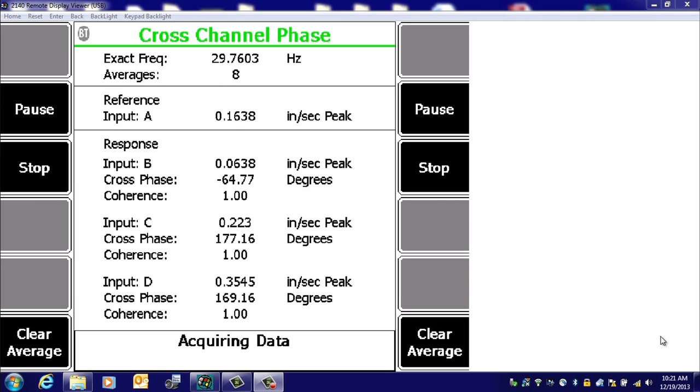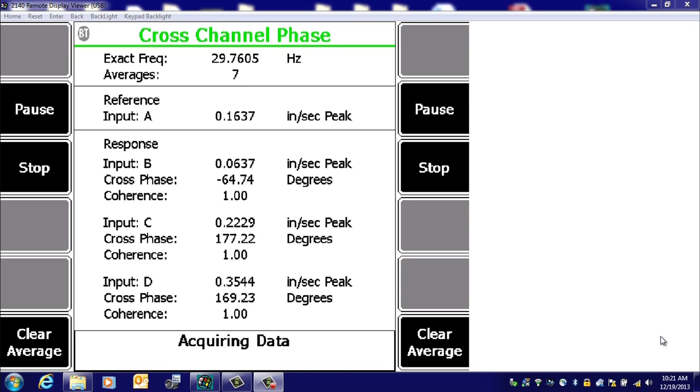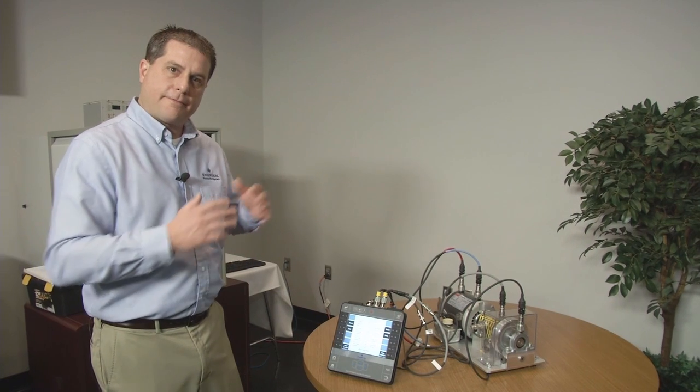But notice the cross-channel phase between A and C. That would be across the coupling is 177. So pretty close to almost 180 degrees phase shift going across that coupling, very indicative of misalignment condition, verifies what we suspected from using our fault frequencies and cursor to mark the two times line frequency peak in the spectrum.